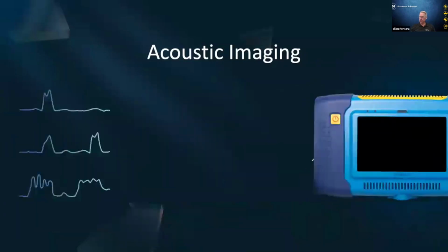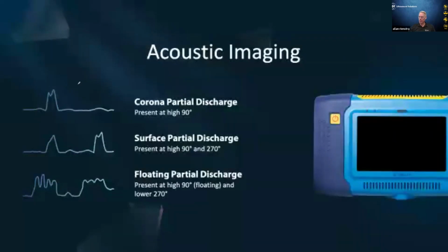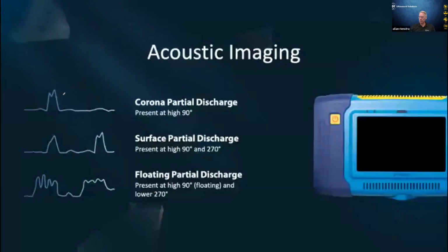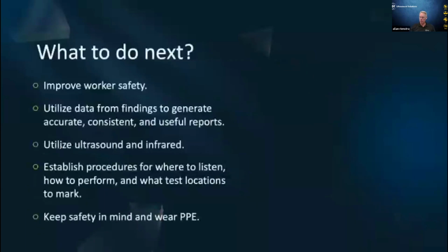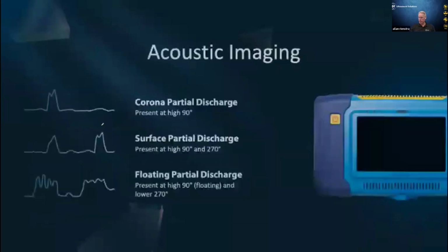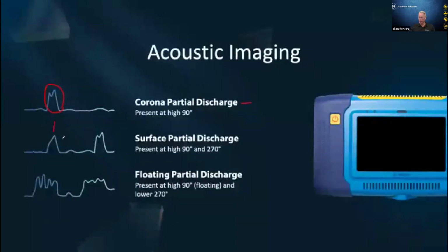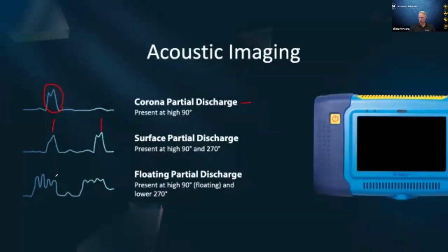And so, like I said, the phase resolved partial discharge, or the PRPD, we can see when it's corona partial discharge, we just see it at the 90 degree aspect of the phase. If it's surface partial discharge, we'll see both at the 90 and the 270. And then if it's a floating partial discharge, we're going to see the same pattern, but it's going to be extended out.